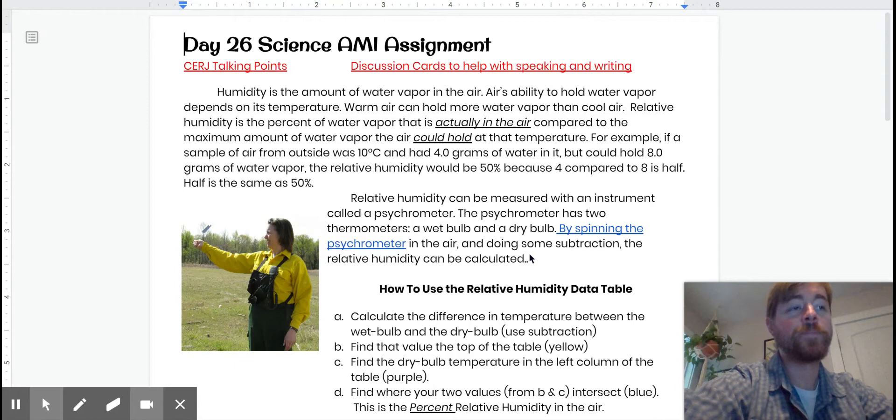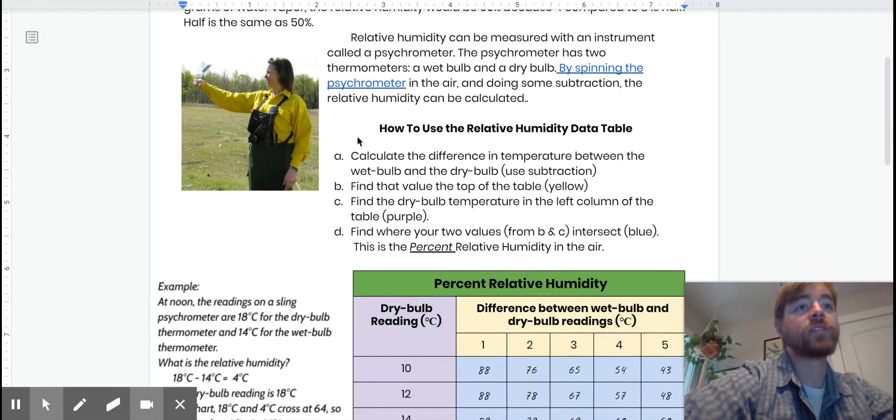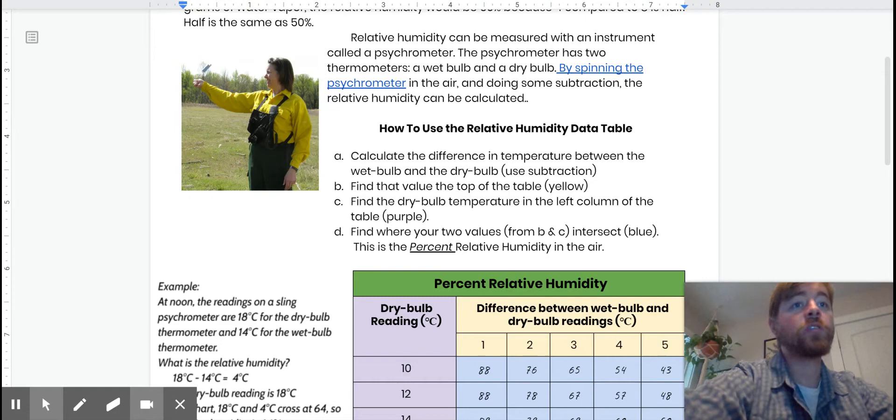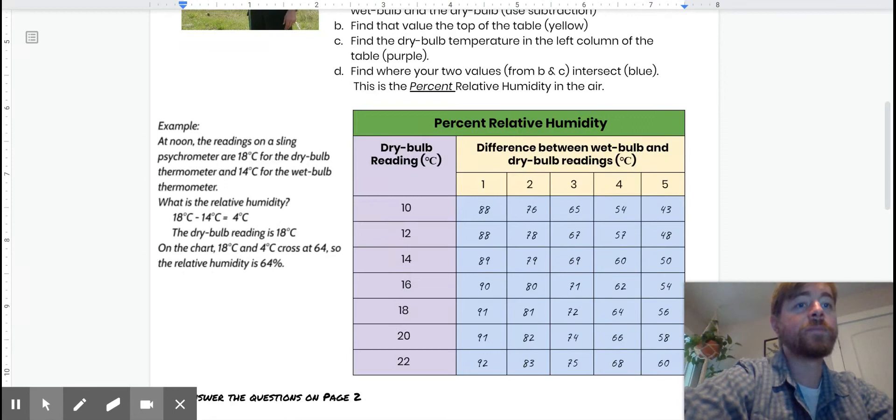In a little more detail, let's read about how to use a sling psychrometer to get relative humidity. First we calculate the difference in temperatures between the wet bulb, that's the one with the little sock on it, and the dry bulb, the actual air temperature. So first we subtract one from the other. Our second step is we find our value at the top of this table. So we look here, was our difference in temperature one, two, three, four, or five. Then we find the dry bulb temperature in the left column in Celsius. And then we find where those two values intersect. This is our percent relative humidity, how much of the water that could be in the air is actually in the air.